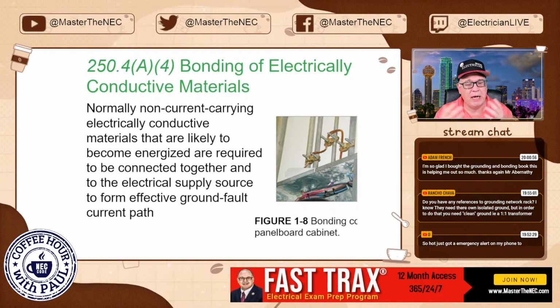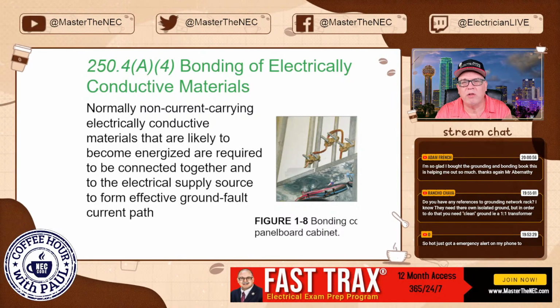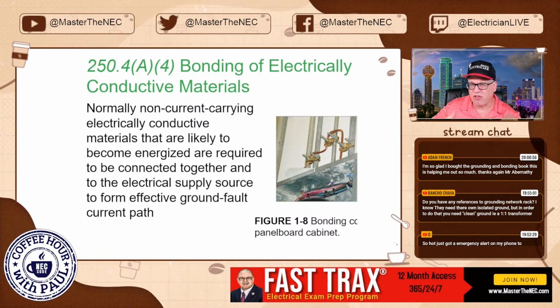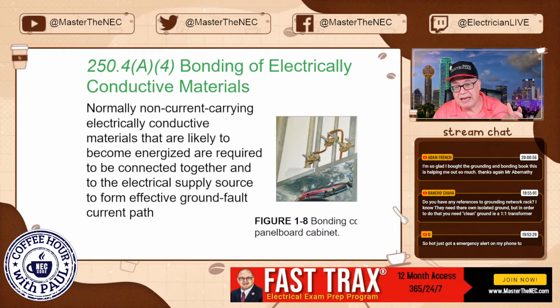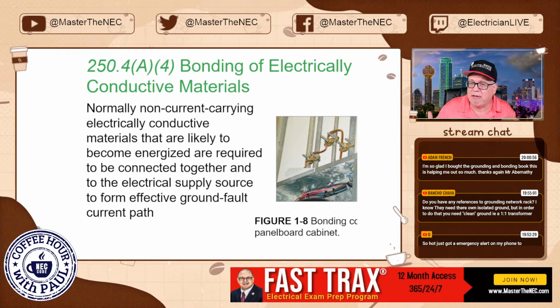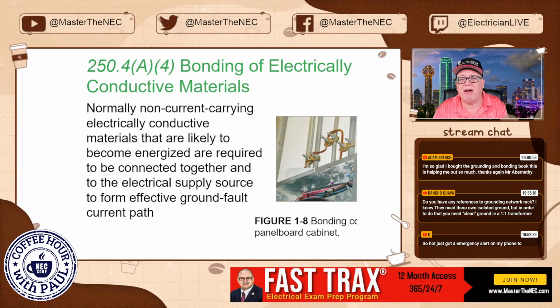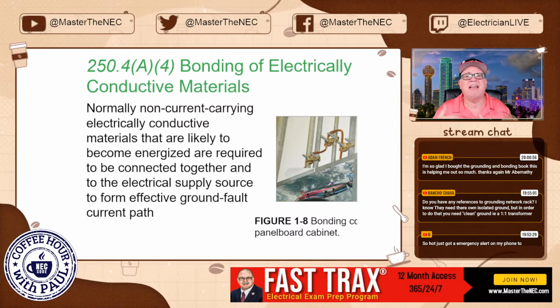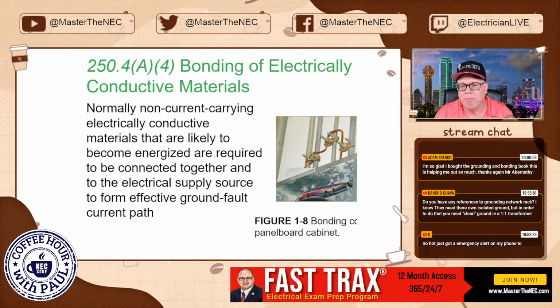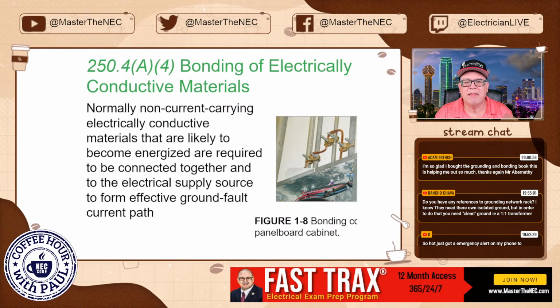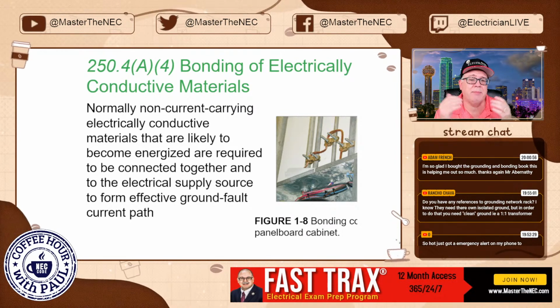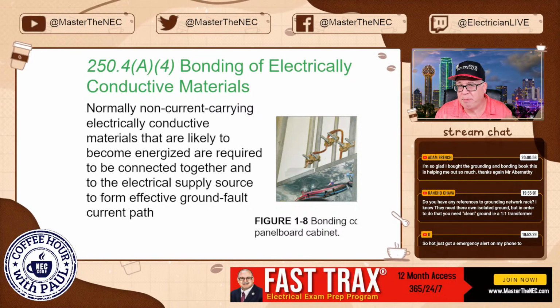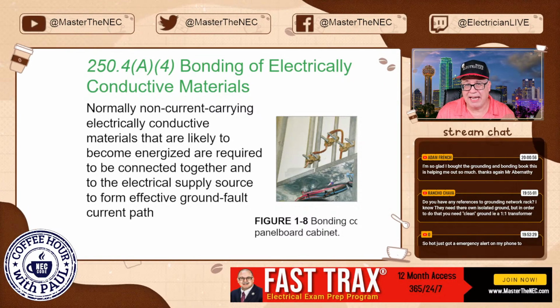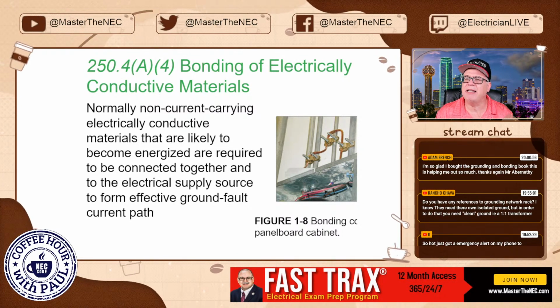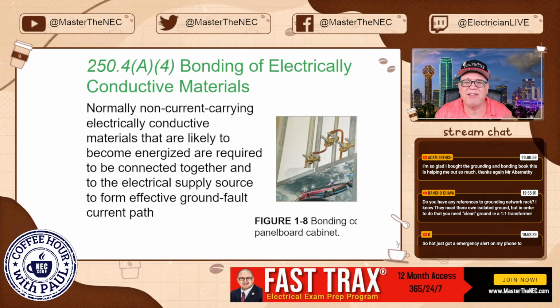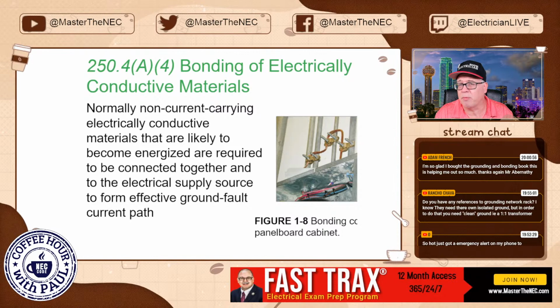You're not going to bond it unless it's what? It's likely to become energized. Now, 250.104 gives us allowances. If I'm bringing a branch circuit to a piece of equipment that has a gas line and my power running to it, and I run an equipment ground, well, I can use that equipment ground to bond and make that connection without doing anything special. And that's in 250.104. But who determines what is likely to become energized? Well, I can tell you this. If I've got a piece of equipment with both a gas line and an electric line running to it, there's a high probability, because of how they merge together, that it is likely to become energized. The good news is 250.104 gives us some provisions for that.